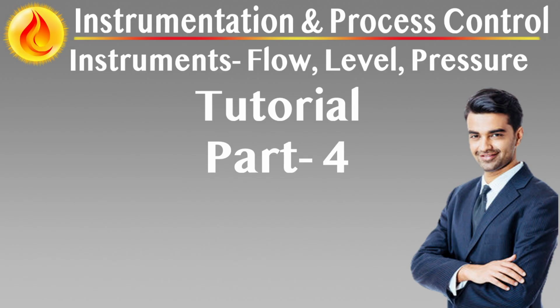venturi tubes to prevent erosion or fouling. Verification of transmitter calibration, particularly if operating across a wide turndown or under temperature variation. Drain and vent line integrity checks to avoid signal distortion due to trapped air or fluid. Conclusion. Differential pressure flow meters remain a cost-effective, flexible, and proven solution when correctly engineered. Their performance is highly dependent on proper sizing, installation, and impulse line management.